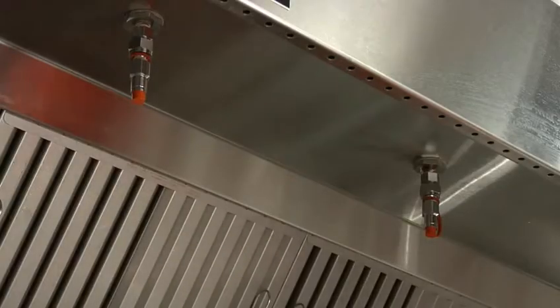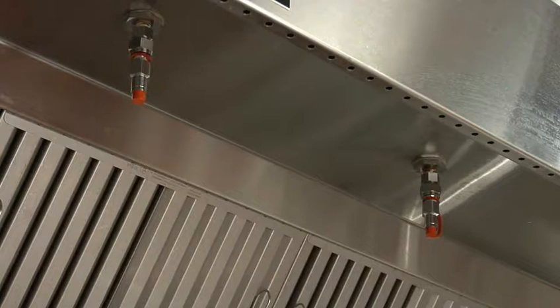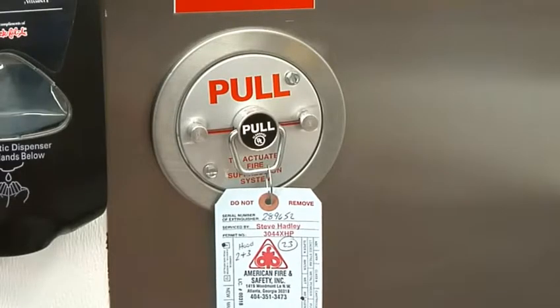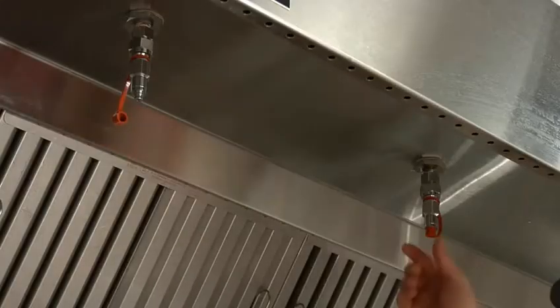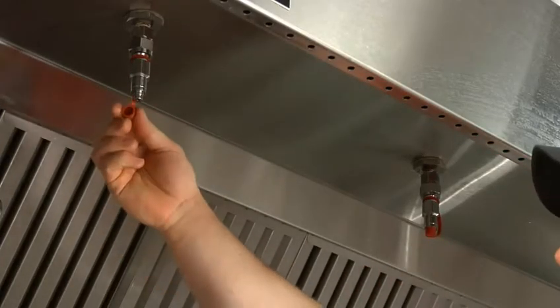The first is called an Ansul wet chemical fire suppression system. This system is installed above cooking equipment. It's set to activate automatically in the event of a fire, and it will shut down any power and fuel supply to help control the fire. The Ansul system has a manual pull station that can be used to activate the system if the automatic feature fails for any reason.